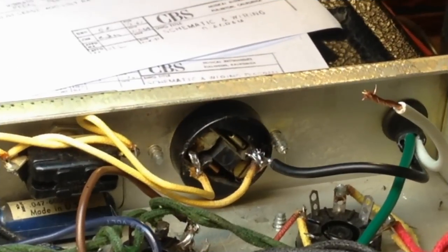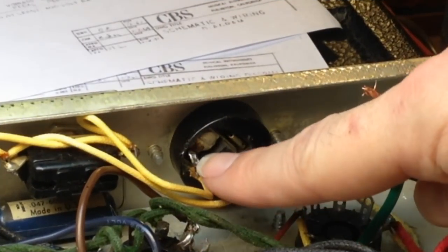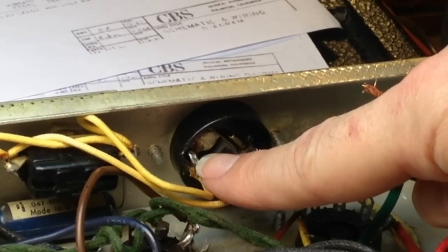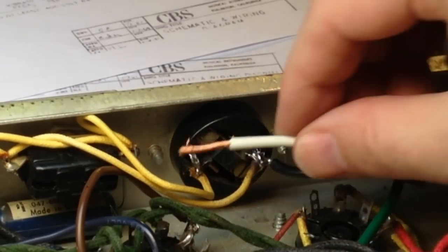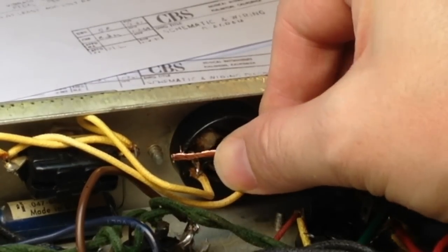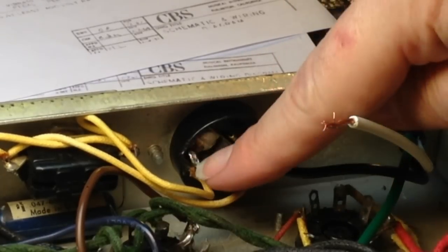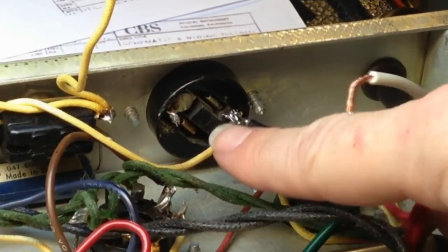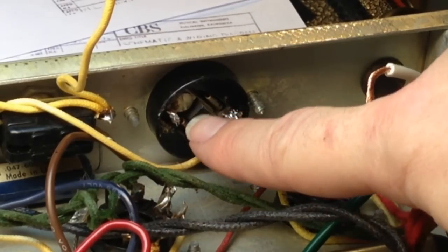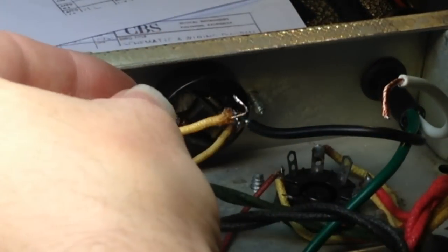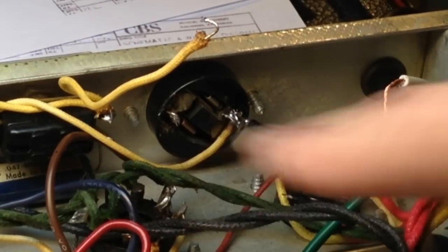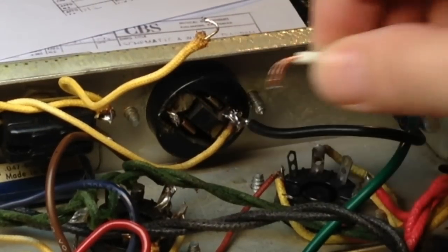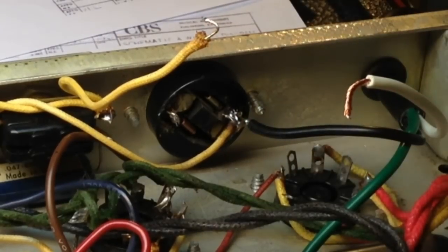Let's do the other one. Okay, I'm having a little bit of difficulty finding the hole on this terminal. And there's a temptation, you know, just to lay this up against there and just to solder. But you never want to do that. You want to make sure you get a good, strong connection through the terminal hole and wrap it around. If you're having trouble getting either of your leads through the terminal, sometimes it helps to remove the existing wire. And that allows you a little more access. And then you can re-add the wire later. So we're going to try it this way.